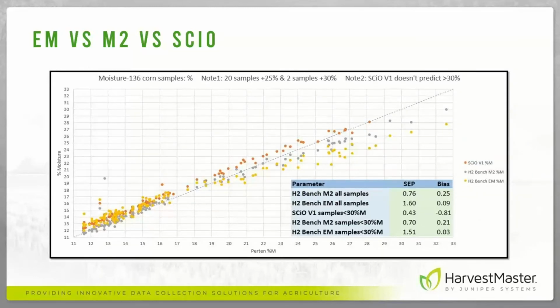And then this last data set is really interesting. Many of you might be familiar with the release of our M2.0 moisture. Prior to 2021, we were using what we called, internally, the EM method, where we have an algorithm we predict moisture with. In 2021, we came out with new algorithms that we call M2.0. We wanted to see how EM and M2.0 compared to a SCiO device. In this case, we had 136 corn samples, many above 25%. We had 20 samples over 25% and 2 samples above 30%. We ran them through those devices and predicted with EM moisture, M2, and a SCiO.